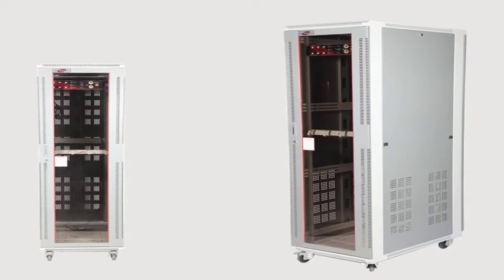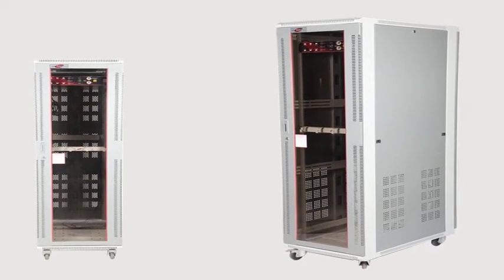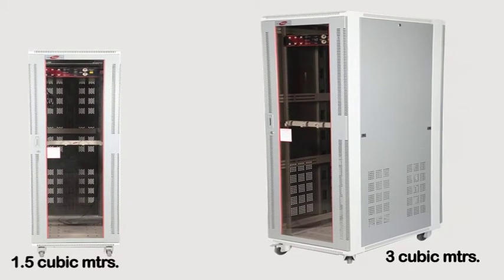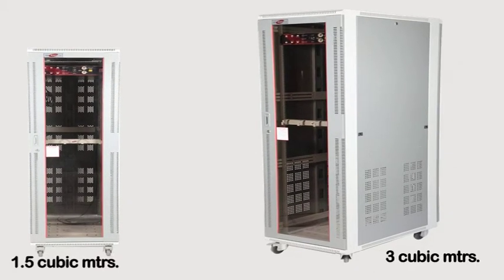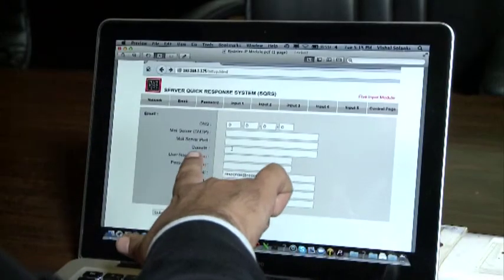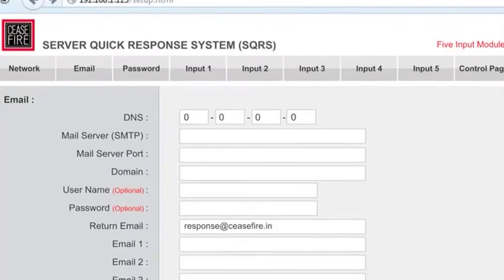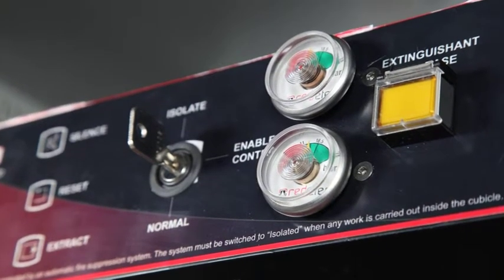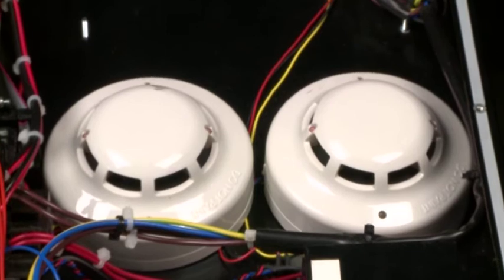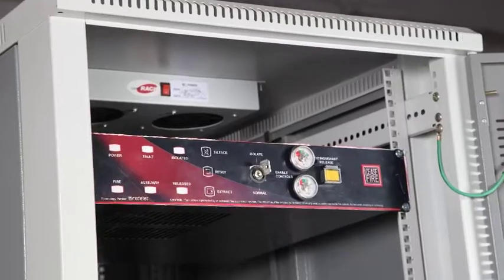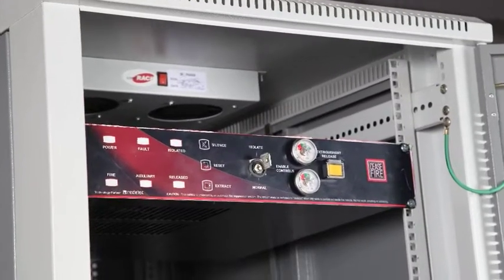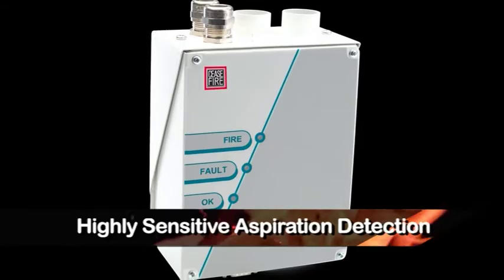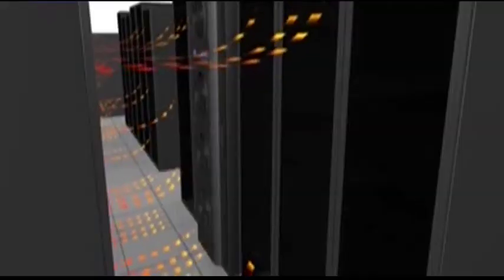Available in two variants, each in 1.5 cubic meters and 3 cubic meters. Both sizes come with optional integratable IP modules. The ZP range includes point-type optical smoke detection, while the ZA range has high-sensitive smoke detection for high airflow applications.